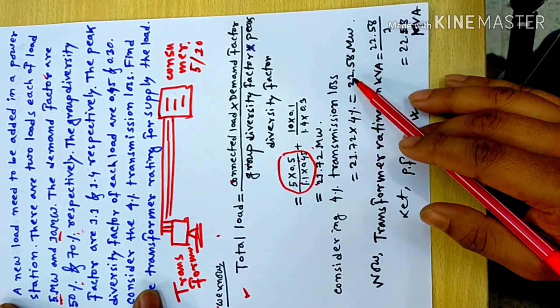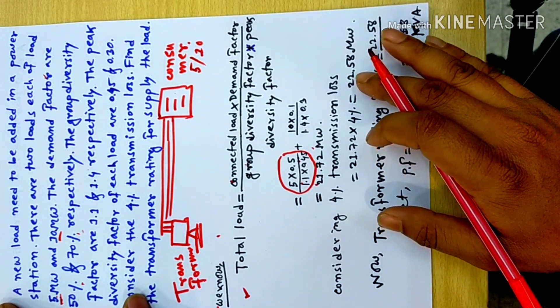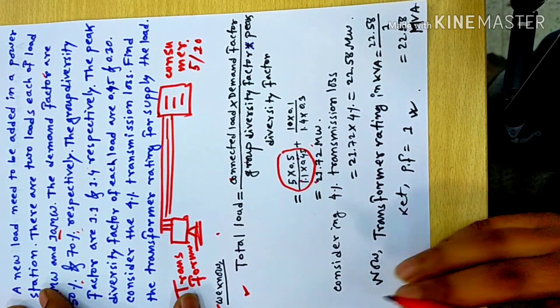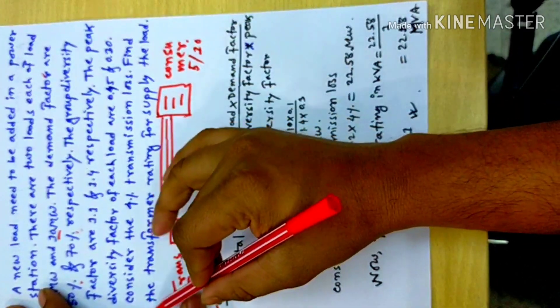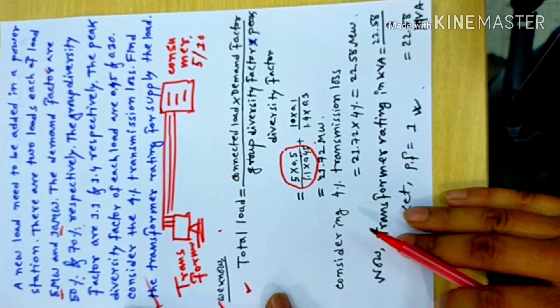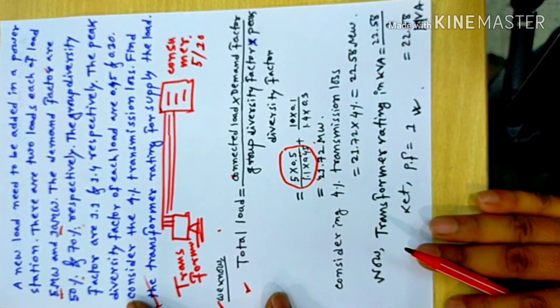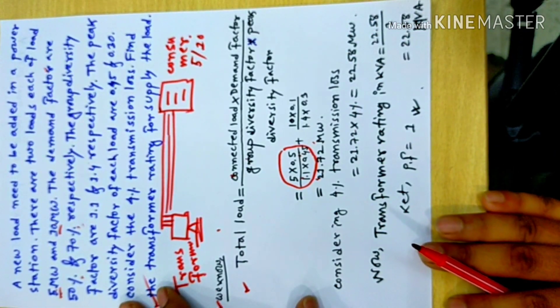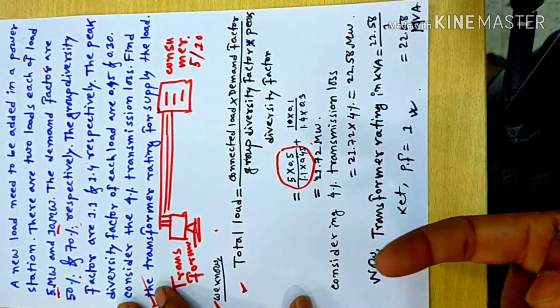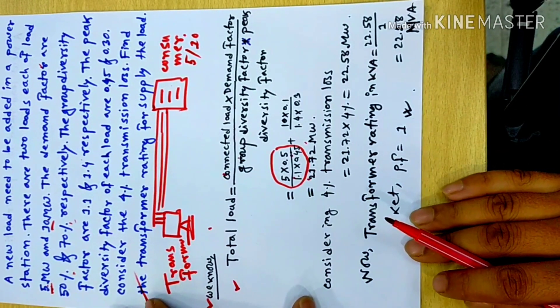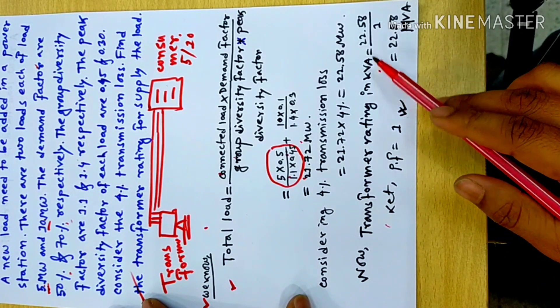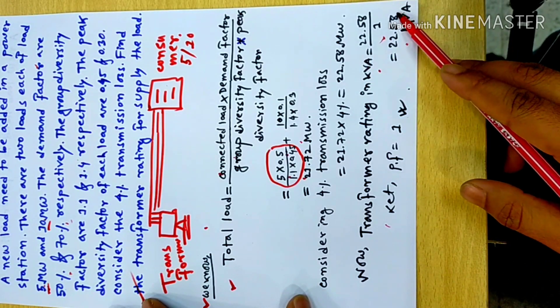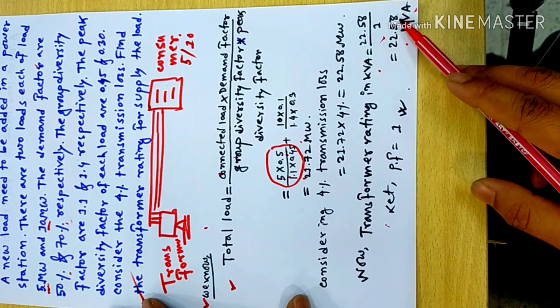We load 22.5 megawatt. This is the total load — that means we supply this load. Now, this is the transformer rating. The transformer rating is not in megawatt, not in watt, not in kV. So the power factor is 1. This is the transformer rating in kVA: kW divided by power factor. So this is 22.58 MVA. This is the transformer rating.